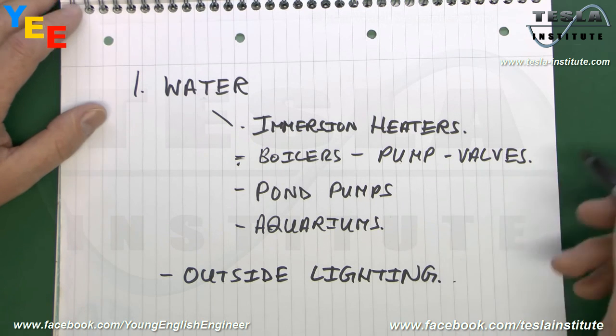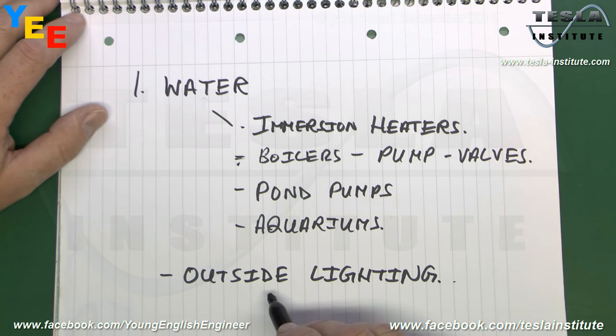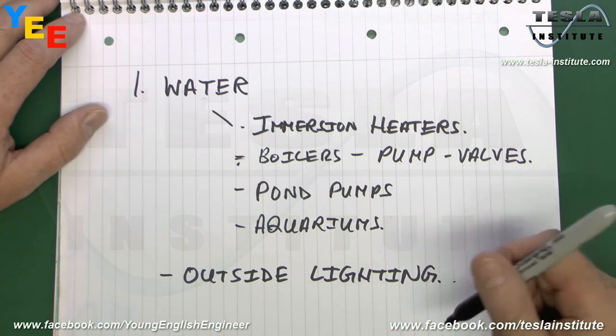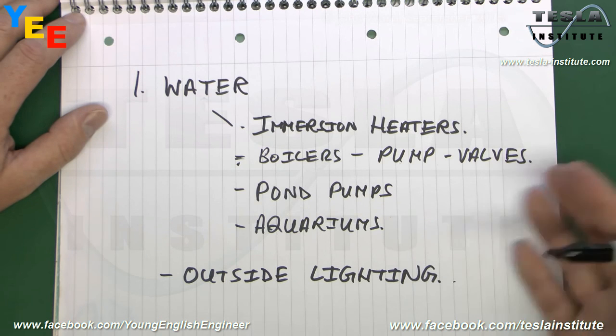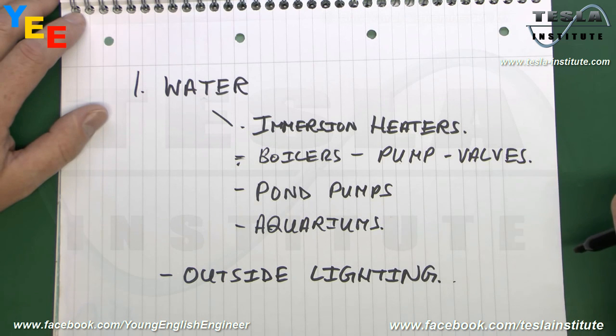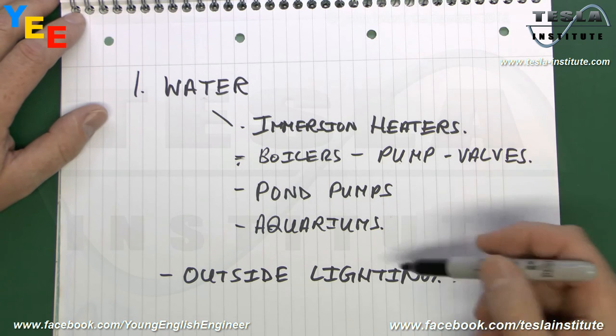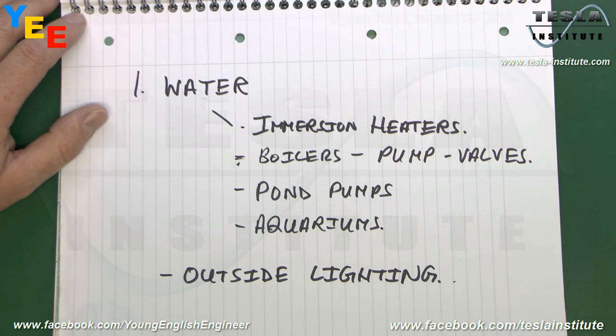And as we saw previously, some outside lights are just basically shoved onto pretty much any old circuit that happened to be nearby, so it could be on the sockets or maybe on the lighting, or maybe just any old thing that just happened to be in the correct location at the time. So outside lighting and anything with water in are the number one things to check, and of course they're by far the most common things that go wrong.